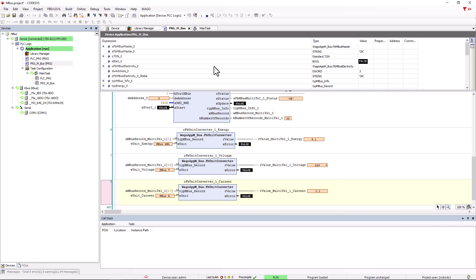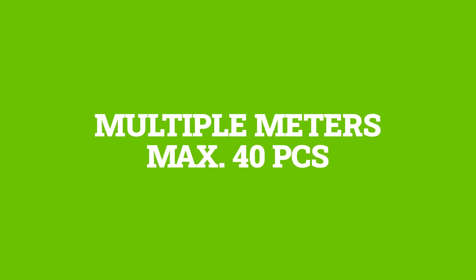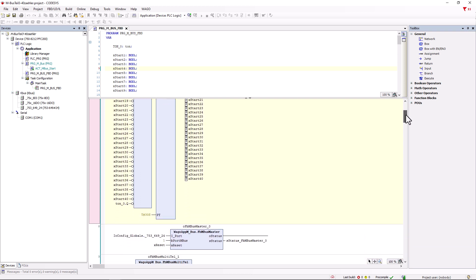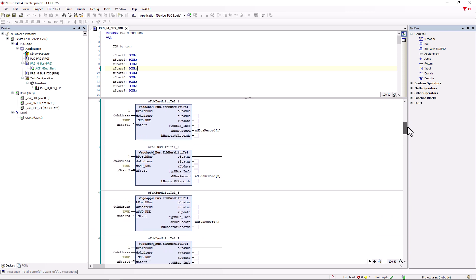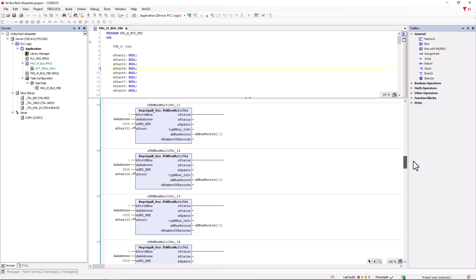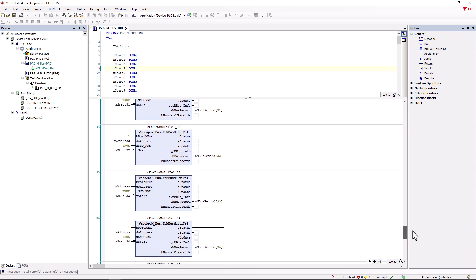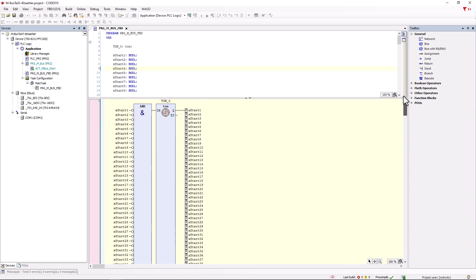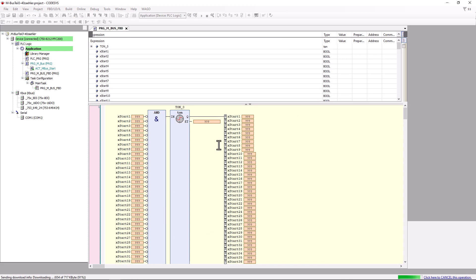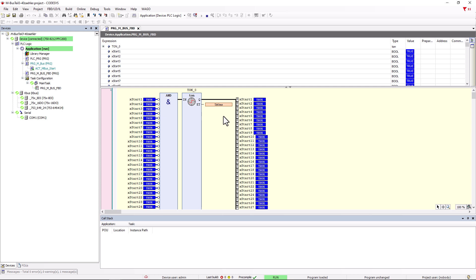This application could be expanded as it is for multiple meters by creating additional Multi-Tel modules with xStart variables. Here we did that for 40 meters which is the maximum possible number of meters on a WAGO MBUS module. Here is the AND link of the Start variables to the TON function block and here is the list of all Multi-Tel modules. When we start the program now we see how the TON module sets all xStart variables to true after the time has elapsed and how the master module processes one query after another and the respective xStart variable is set back to false by the corresponding Multi-Tel module.